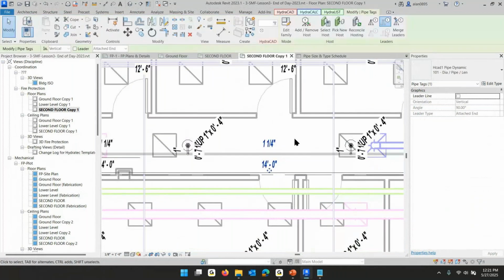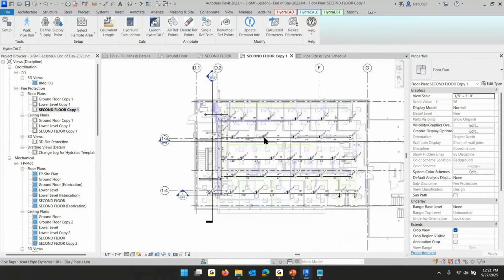Are we talking about that block? The calc block, the fire protection system command block we put in. So when we're changing these pipe types, is that automatically getting updated, or do you have to run the calcs again? No, if I change diameters, now in this case, I changed 3 to 2.5, the block is up to date. But if I change 1.25 inches to 1.5 inches, now that calc is incorrect. I need to rerun that calc. Okay, cool. Thank you.